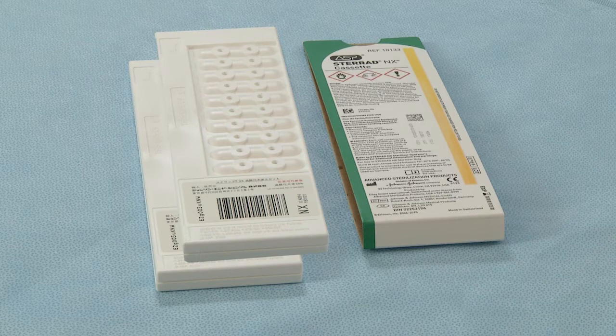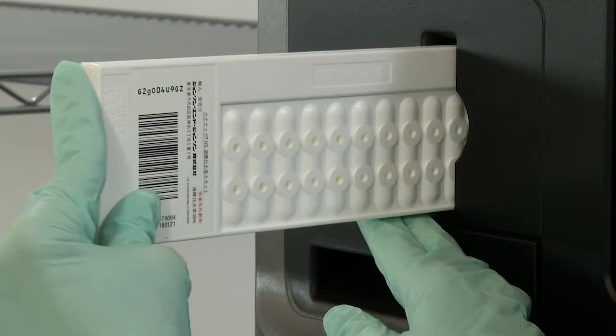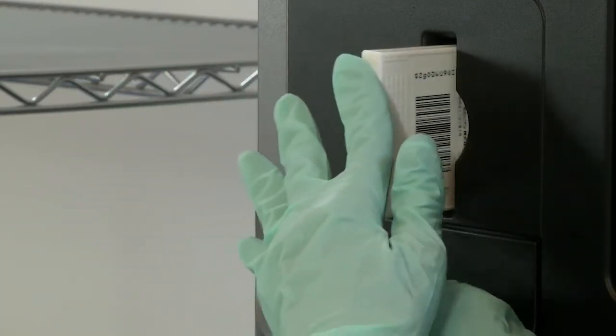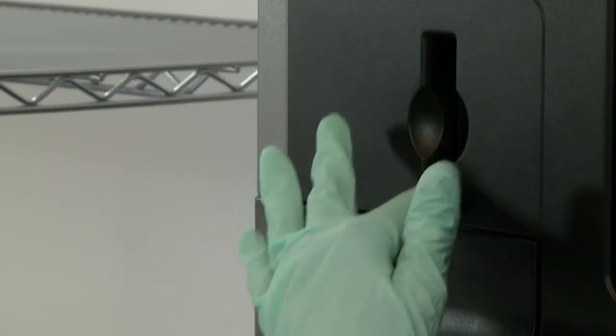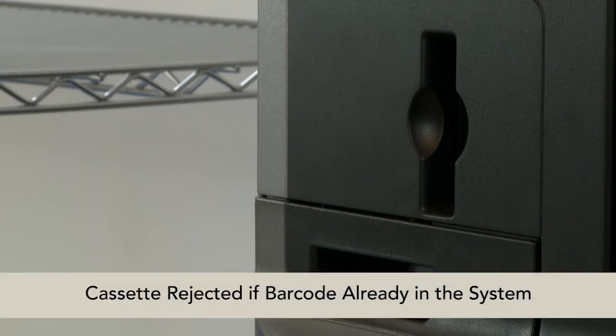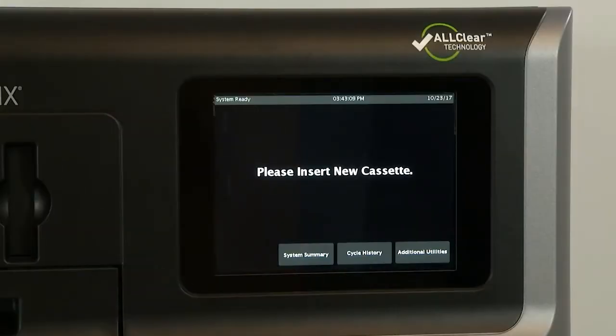The STERRAD NX sterilizer will compare and store the barcode information to a database when a new cassette is inserted into the sterilizer. The sterilizer will reject the cassette if the database already contains a barcode with the same information. If a new cassette is required, if the cassette in the sterilizer is expired, or if there is no cassette installed in the sterilizer, the following steps should be followed to insert a new cassette.